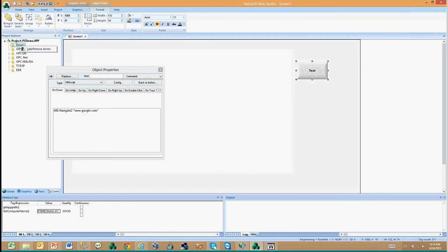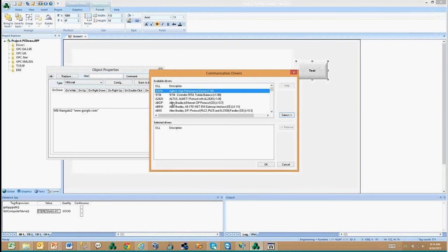For example, the Modbus slave driver, this one, supports unsolicited messages, so the device itself can be a Modbus master and push data to the InduSoft driver. And in the driver worksheet, you can assign tags to specific addresses from the PLC, and when the values are received, the InduSoft tags receive the values.